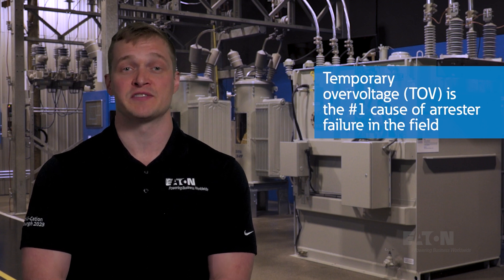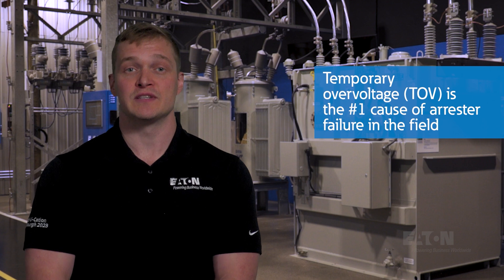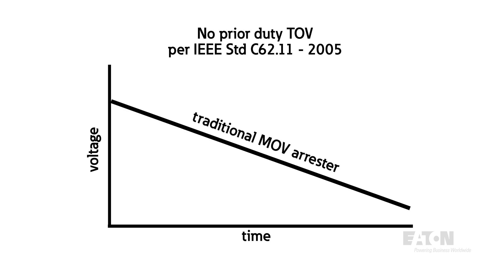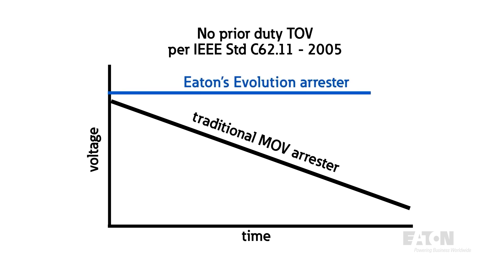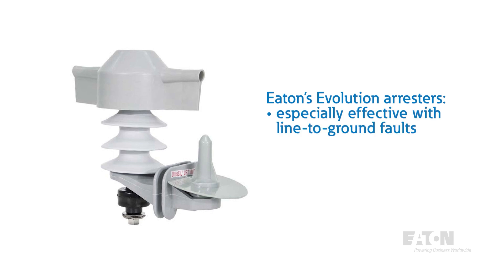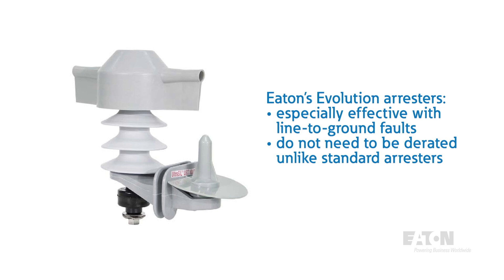Temporary overvoltage, or TOV, is also critical to performance, because it's the number one cause of arrestor failure in the field. TOV can be described as the strength of the arrestor, or how much overvoltage it can handle. Typically, this capability decreases as the time duration of the surge increases. But Eaton's Evolution Arrestor is the only type of its kind in the industry where surge duration doesn't affect the TOV capability. This is especially important in single-phase line-to-ground faults, which cause a voltage rise on unfaulted phases. This continuous overvoltage will cause standard arrestors to fail, so arrestors usually need to be derated to account for these faults. However, by having a duration-independent TOV rating, the Evolution Arrestor eliminates the need to derate and gives utilities the ability to use smaller kV sizes.